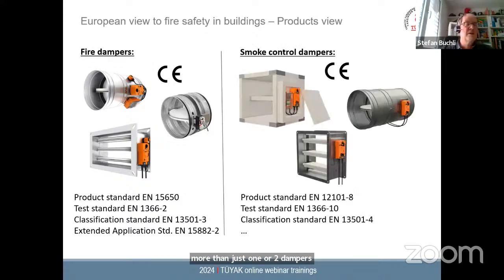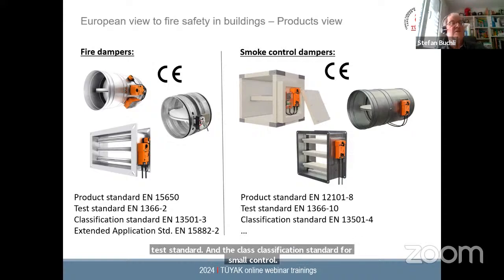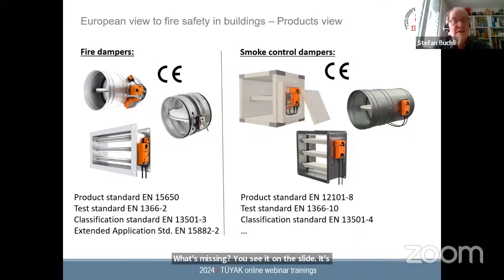On the smoke control side, you see quite a similar picture. So the structure is the same actually. You see the product standard again, giving you some clues what a smoke control damper is. In this product standard, you also find different applications of smoke control dampers, because there are 3 different applications mentioned in there. You find as well the test standard and the classification standard for smoke control dampers. What's missing, you see it on the slide, is the extended application standard. This standard is currently on the CEN level, on the European Commission level. It's currently under discussion if work on this 4th missing standard should be started. I hope they will start it because it gives great help for the manufacturers of the dampers.